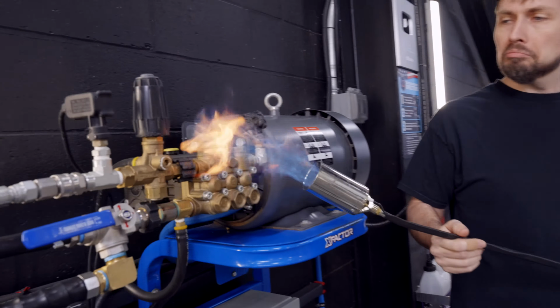We'll create the issue. Dirt or hard water might give you the same results. Water gets sucked in, comes in, goes through there, but if it's hung up, when the piston goes up and down, the water will just go in and out, in and out. I've seen little pieces of rubber or things get stuck in those check valves and hold them open, and that'll cause pulsation as well.